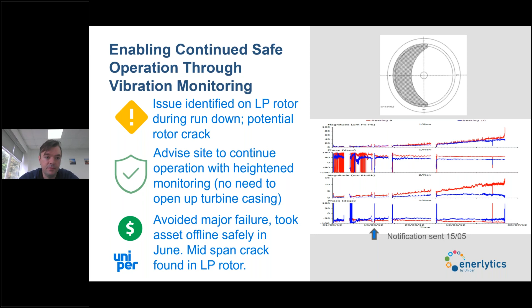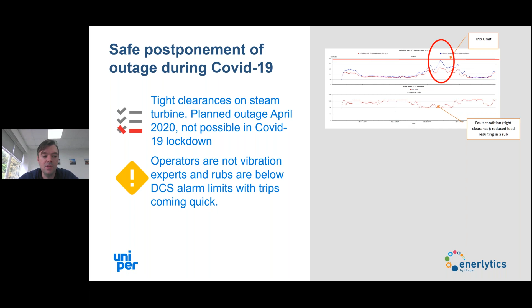The final case study I've got is on postponing an outage in COVID-19. So in this example here, we've got some tight clearances on the steam turbine, and they planned to expand those clearances in April 2020, but that wasn't possible. Now, the operators are not vibration experts, and these rubs that happened were well below and within the DCS alarm limits. However, when the trip happens, it comes really, really quickly in the space of minutes, often when the operator is not ready. And a trip in this market is particularly heavily penalised.